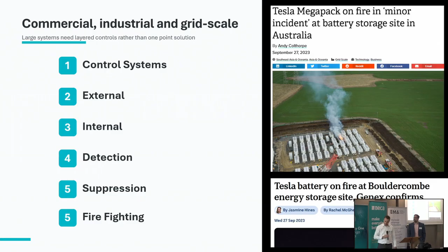In terms of how you actually set these things up, and Nikk talked about good early thought and how we plan them, that's really all it comes down to. If you're putting these units external, space them out. If one catches fire, the manufacturers tend to have recommendations on how close you can put these things to limit that spread and give firefighters the ability to stop fire spread. If you're choosing to put them into a building, there's more risk there.